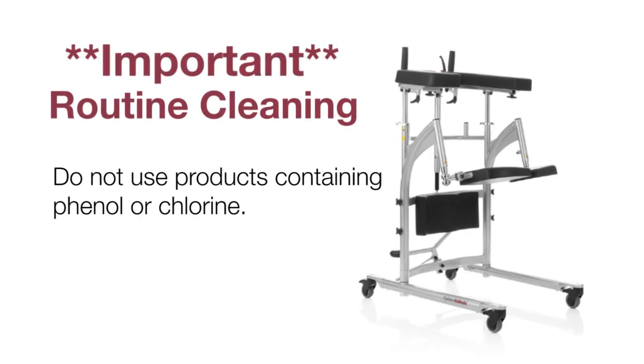Routine cleaning of the walker should be done with common surface disinfectant such as water-based ammonia compounds or quaternary compounds. Do not use products containing phenol or chlorine, since the nylon parts may be damaged. Assure that the wheel casters are free of dirt and hair.